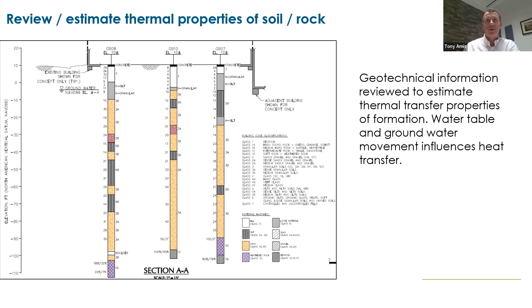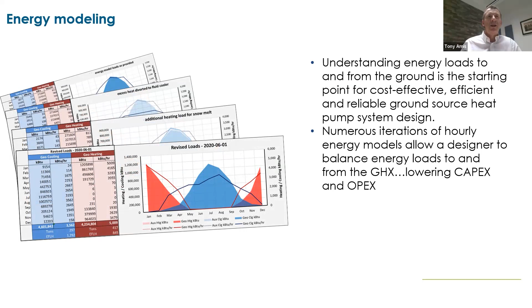The absolute crown jewel is an energy model. The mechanical engineering will provide us with 8,760 hours every year, and for every one of those hours what we want to know is how much heating and cooling is being called for in the building. That enables us to do quite a lot of iterations and work out what the optimum geothermal system is.